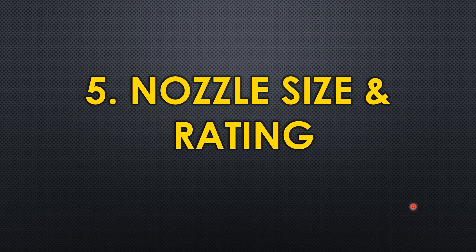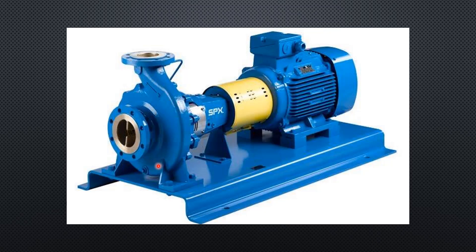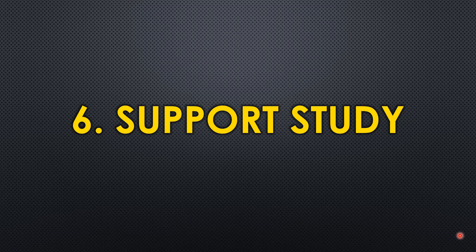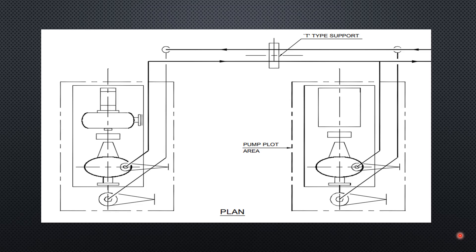The fifth parameter is nozzle size and rating. These are critically important because this is where the piping connects to the pump. For example, your piping spec may call for a 150-rated flange, but the pump delivered could be 300-rated. Before proceeding with pump piping, you must know the flange rating to plan the connection correctly; otherwise you will end up with a major mismatch during construction and face procurement issues.